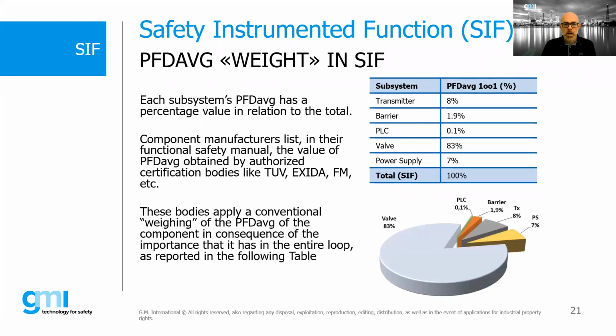In the following slide, we see what weight the individual subsystems have within a SIF. It's important that every single component of a SIF, including the power supply system, is included in the PFDavg calculation to achieve the required safety level. Every single element has its own percentage weight, which must be considered.